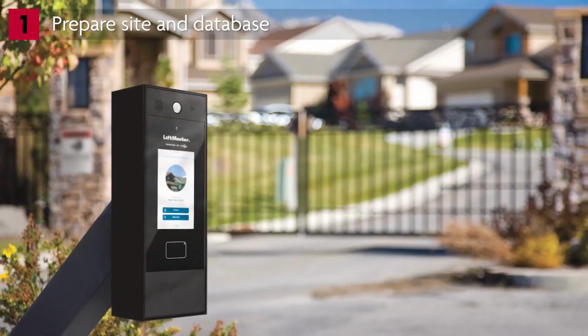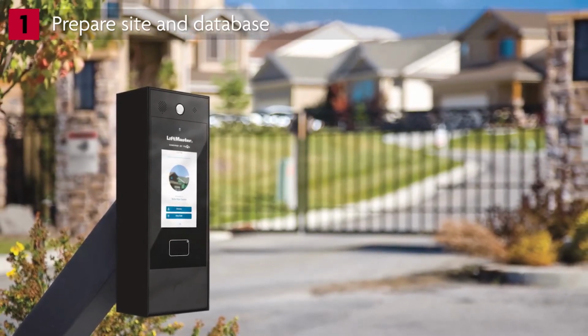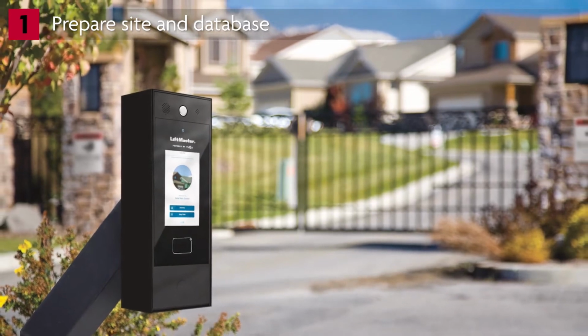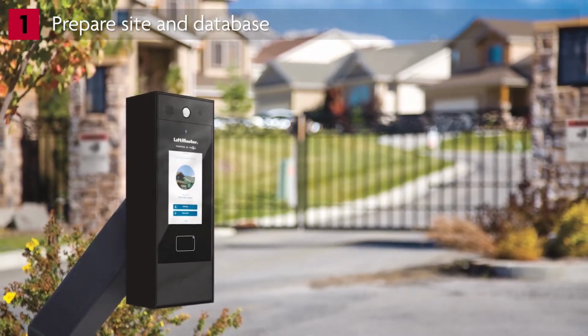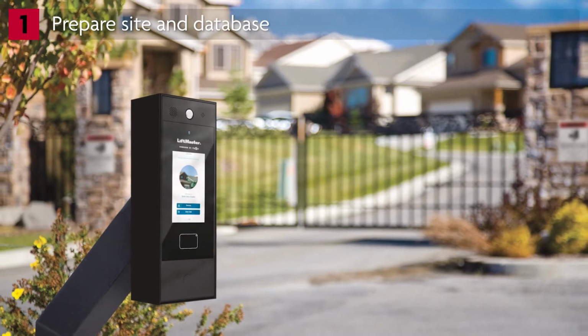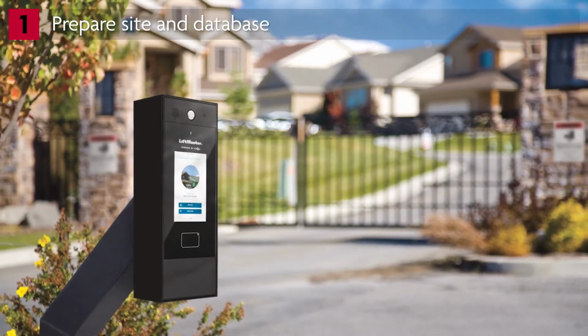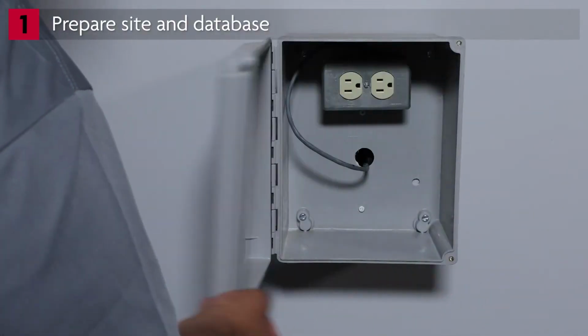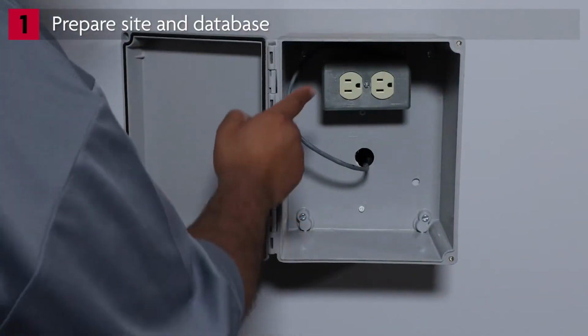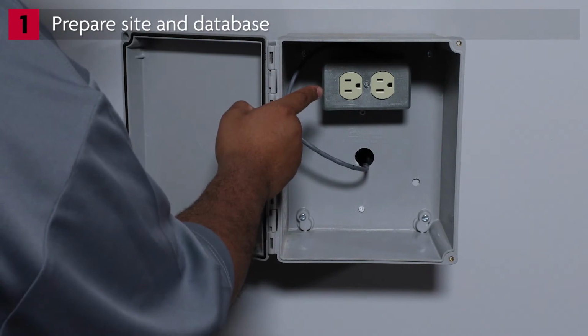As you walk through the job site, if the CAPXM will be used to control LiftMaster gate operators, make sure the physical location meets UL 325 and ASTM F2200 requirements where these standards apply. Make sure AC power is available and meets these requirements. There needs to be a dedicated 120-volt AC outlet rated for 10 amps. Depending on the site configuration, the outlet may be located in a separate room, requiring a run of DC wiring to where the CAPXM will be mounted.